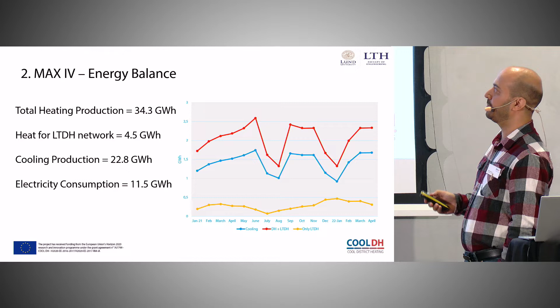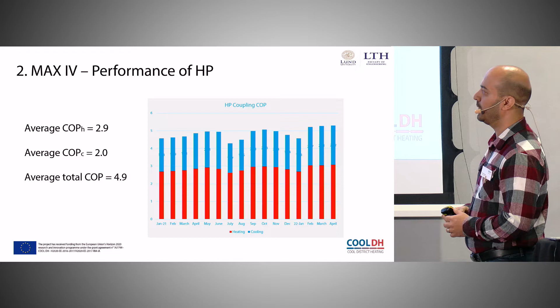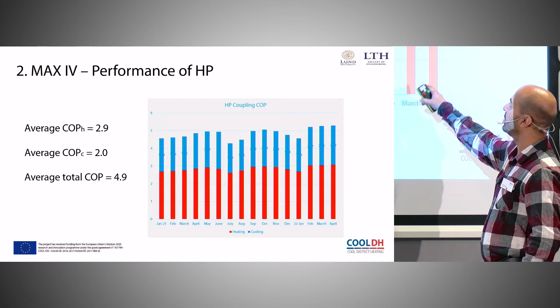And then the performance of the heat pump system, because it's not just one heat pump there, it's a coupling system of heat pumps. COP for heating, you can see in the red column, is on average 2.9, and COP for cooling on average is 2, which you can see in the blue columns, and total COP is near 5. And also, as you can see, the performance of the heat pump has increased during the last 3 months.